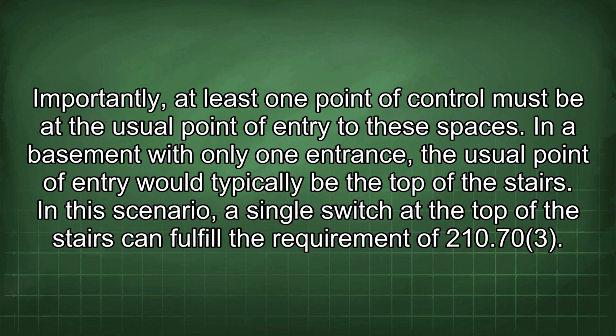Importantly, at least one point of control must be at the usual point of entry to these spaces. In a basement with only one entrance, the usual point of entry would typically be the top of the stairs. In this scenario, a single switch at the top of the stairs can fulfill the requirement of 210.70(3).